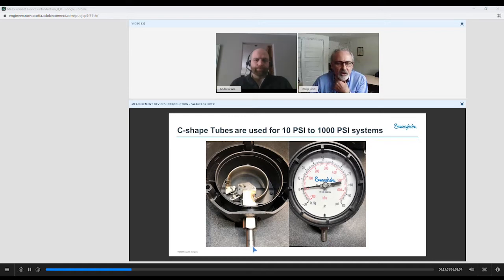In this case, coming from the pressure connection through the socket to the Bourdon tube is all 316 stainless, and you may be able to see that on your slide. So it's 316 stainless in the tube and connection. There's other information laid out on here. This happens to be a 4.5 inch, what's typically called a process gauge.